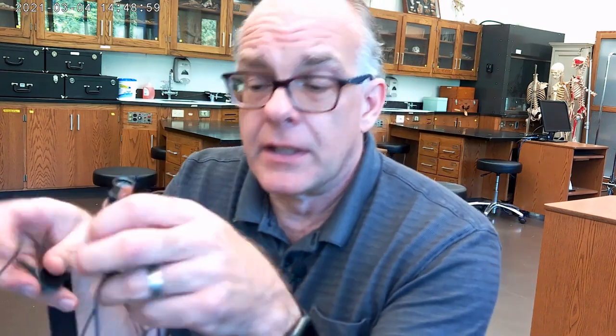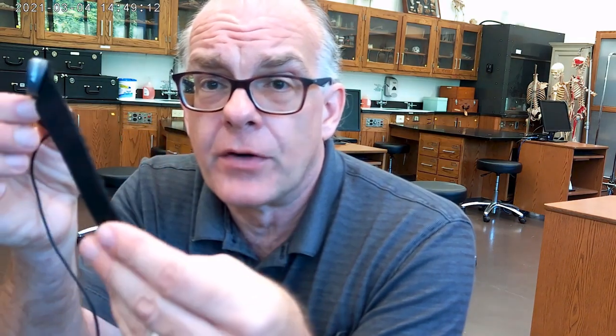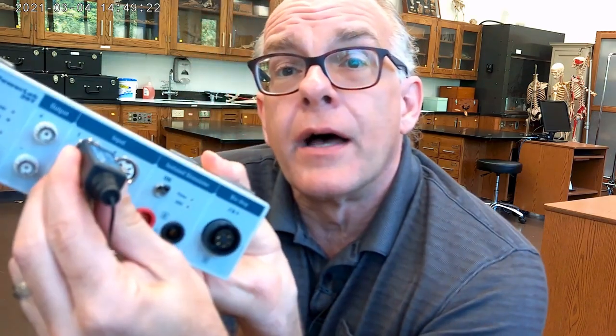The final device is going to allow us to collect the physiological measurements. This is a pulse transducer, and you have an 8-pin DIN connector at one end, and then the pulse transducer, a smooth edge with a Velcro strap on it. Now, what we're going to do is take the 8-pin DIN connector and plug that into input one on the front of the Power Lab system. Again, because of the notch, it's only going to fit in one way. It should fit in relatively snugly, but again, you don't want to force it if you've got the orientation wrong.